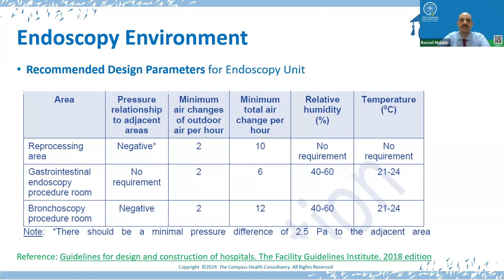In the reprocessing area, we must have adequate space for reprocessing. Jill mentioned having enough space for an additional sink if we need extended soaking. So it is important to address adequate space, appropriate airflow and ventilation, selection and method of disinfection and the chemical sterilant that is used, and an appropriate storage area, which follows the proper workflow. Reprocessing areas should be accessible only to authorized personnel. The workflow should be unidirectional, so we mean by that movement from the dirty to the clean area in order to minimize the opportunity for cross-contamination. And the dirty and clean areas should be physically separated from one another.